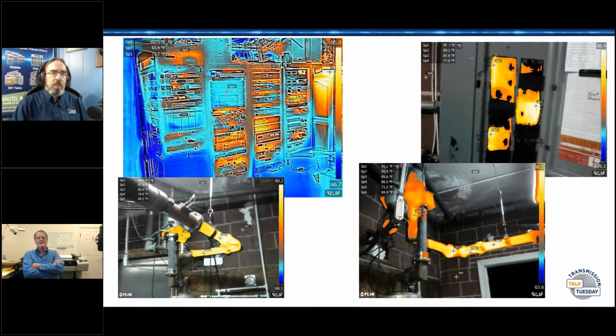If you overlay the real image with the thermal or infrared, it's easy. You can actually see the outline of every breaker, just like in that top left photo. You can tell where one piece of equipment is versus another. If there's a hot spot in there, I could walk in and just eyeball that rack and know which piece of equipment I need to take a closer look at.